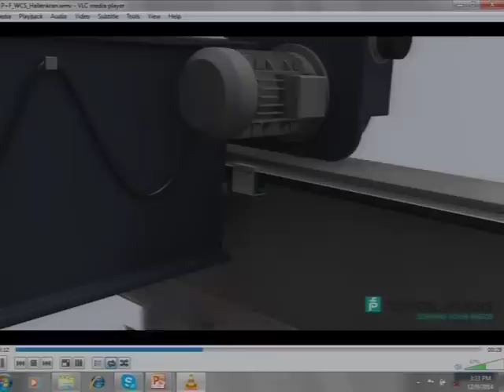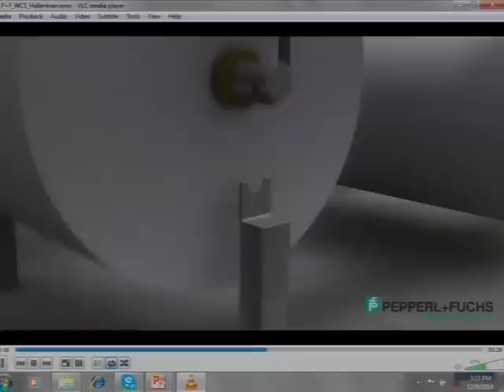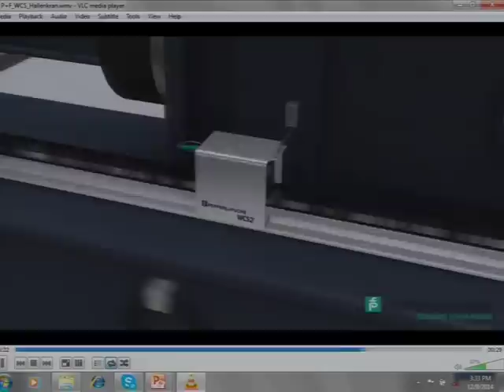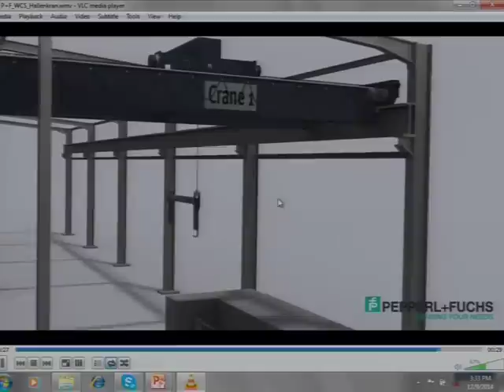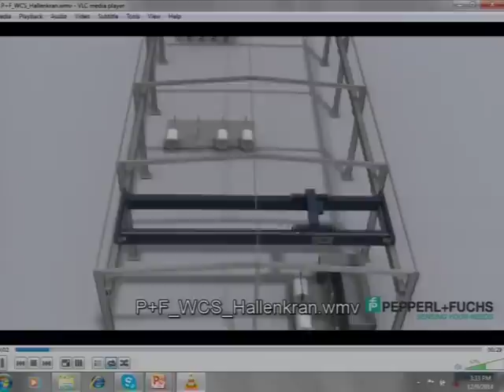For overhead cranes, you need to do the positioning, so that you are picking the component from one position and placing it exactly at the same position. So this is a mechanical rail that is being connected, and this is the head that is moving on top of it, and it will give you absolute position. It is similar to an absolute encoder, because in case of a power failure, it gives you the absolute position when the power comes back. It is not going to restart, or you do not need to go back to the home position. Again, same concept. Instead of a disc, it is a rail.